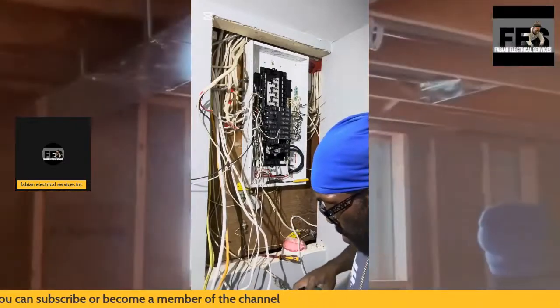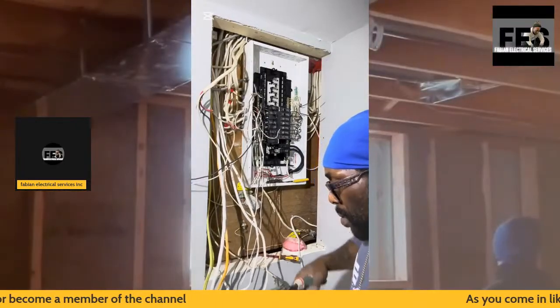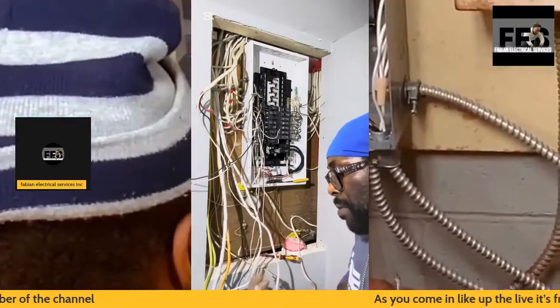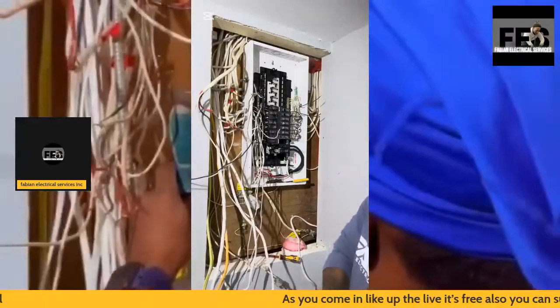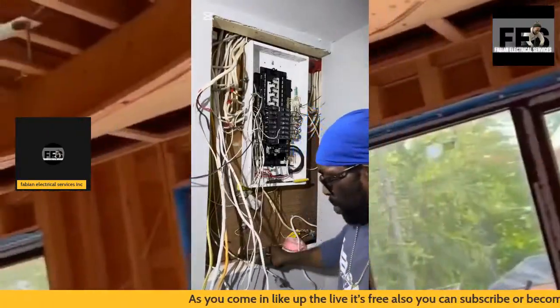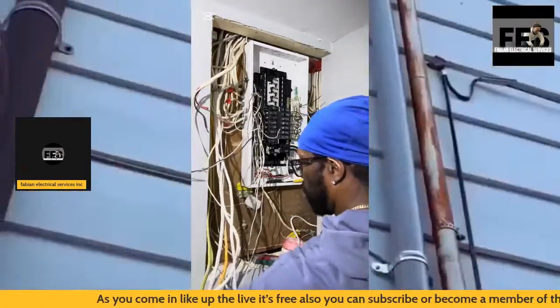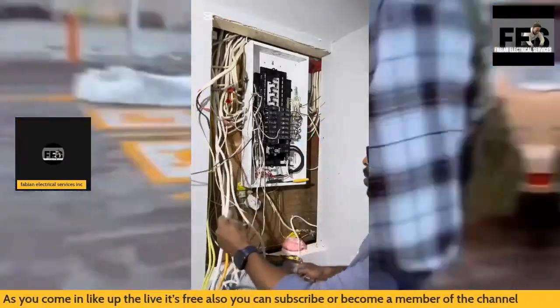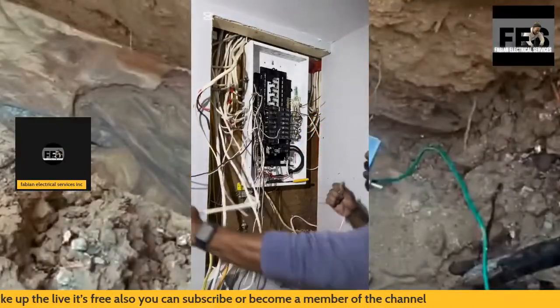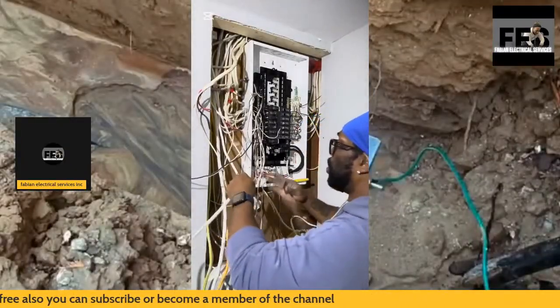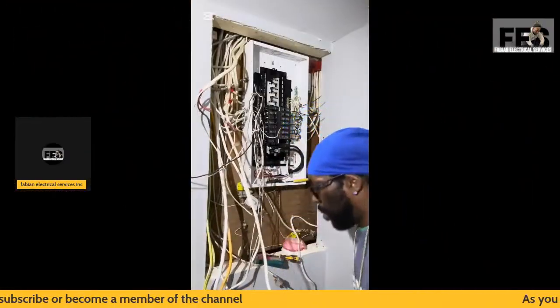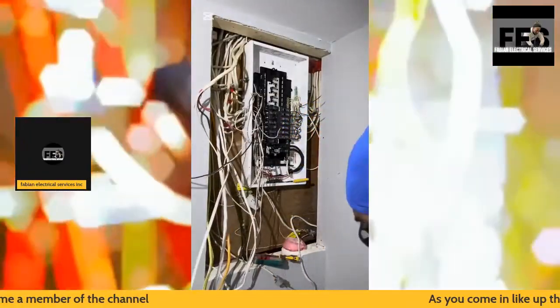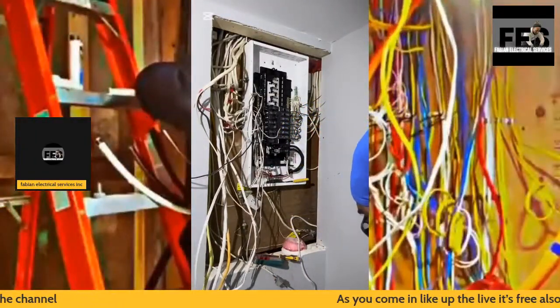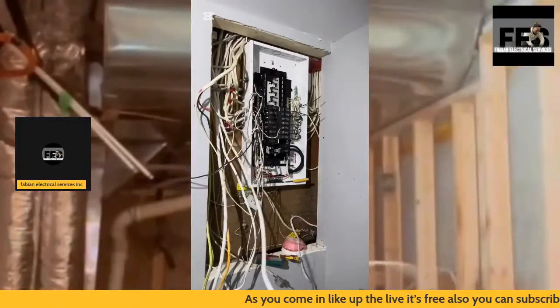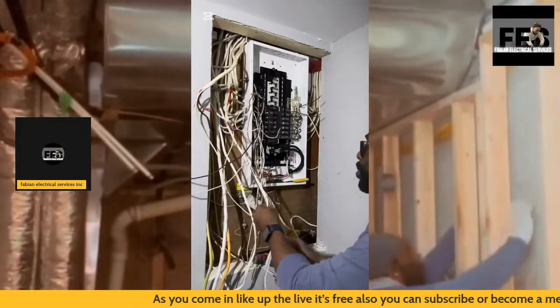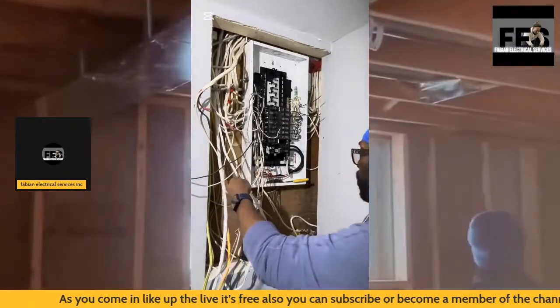So what I do on a job like this is go in before the service is shut down and mark all my wires, making sure everything is labeled properly. That way, once I start installing the new panel and new wires, I'll have my wires marked, and I won't be running around at the end of the job troubleshooting or tracing circuits.